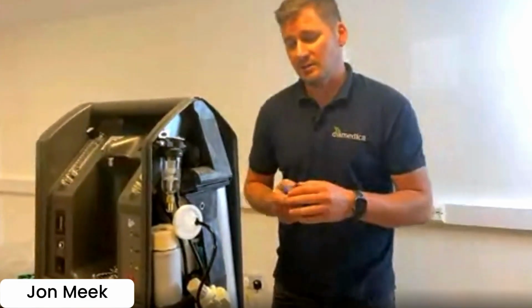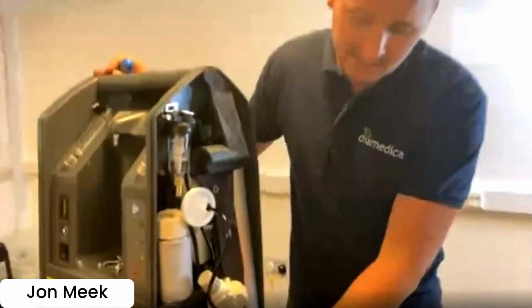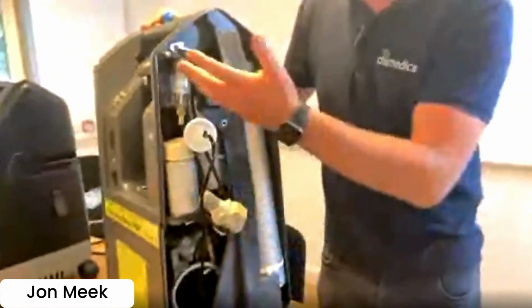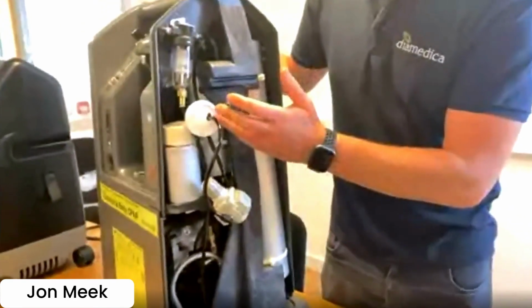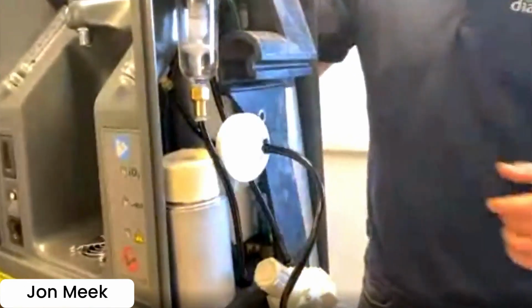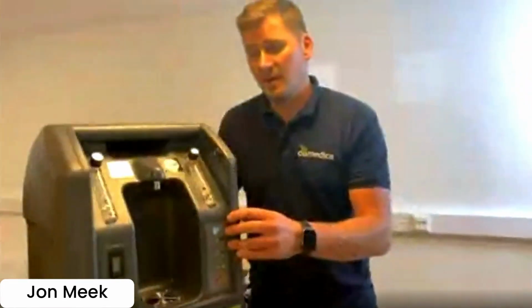delivered through to patients. So it's a very simple tap off from the compressor, water trap, regulator, through the HEPA filter, and then through to the flow meter, utilizing every part of the machine to help it run.